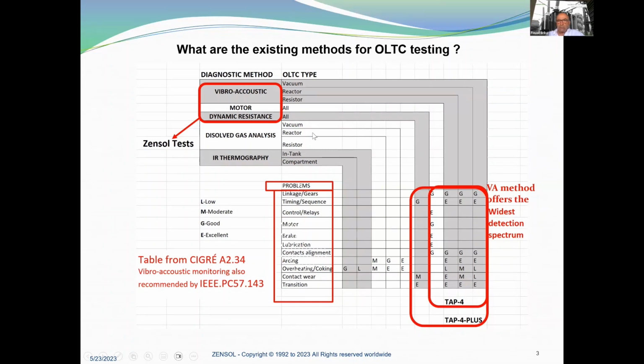And here, each method is good in one field. For example, the brake is very good for the motor drive testing. So here, the Vibro-Acoustic method offers the widest detection spectrum, and this table comes from CIGRE A2.34, and we also have a reference in Vibro-Acoustic monitoring recommended by IEEE. I really recommend that you take some time and study these tables. It's really interesting because it gives an overview of which method is good for which testing problem.